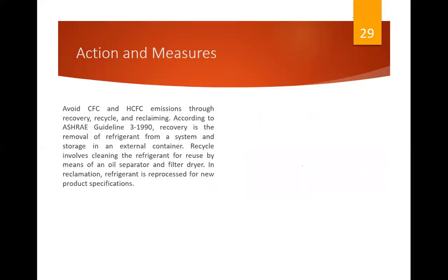Avoid CFC and HCFC emission through recovery, recycle, and reclaiming. According to ASHRAE Guide 3-1990, so we have a siguro latest ito. Recovery is the removal of refrigerant from a system and storage in an external container. Recycle involves cleaning the refrigerant for reuse by means of oil separator and filter dryer. In reclamation, refrigerant is processed to new product specification.